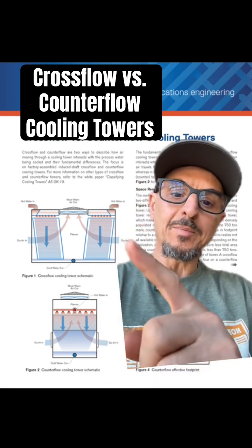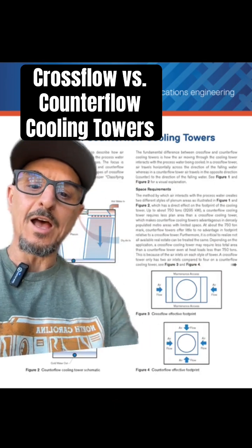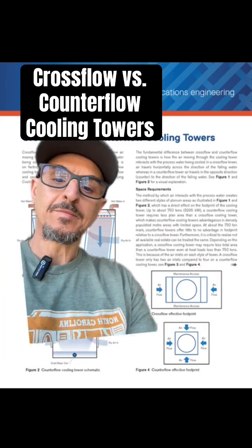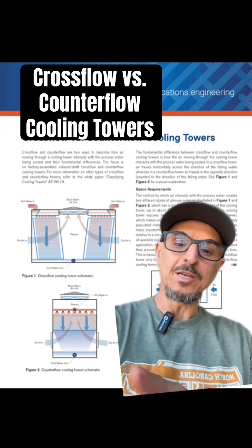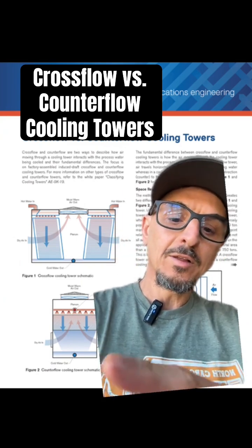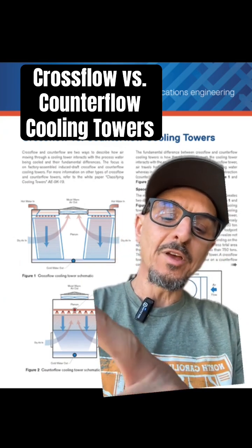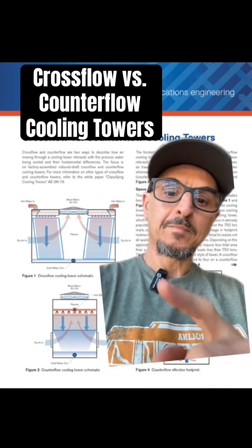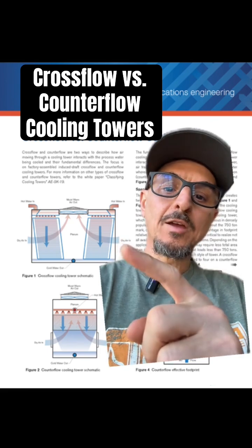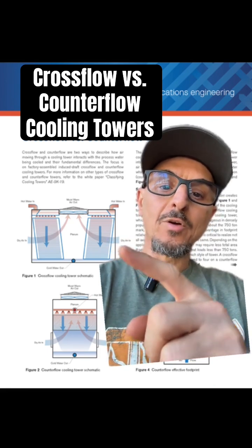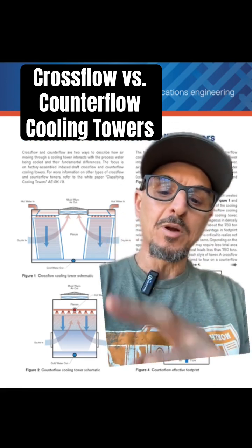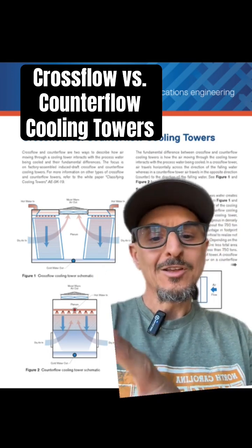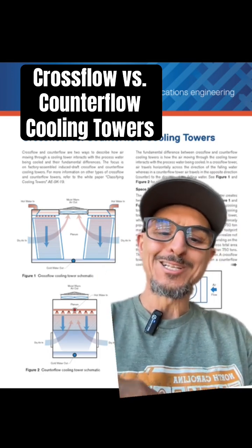In a cross flow application, the air is pulled into the sides of the tower as shown here. In a counter flow application, the air is pulled in through the side, but it comes up through the bottom of the fill. I like to remember this by thinking of cross flow as the air going across the water that's falling — it's perpendicular. And then in the counter flow, the air is going the opposite way, hence the term counter flow.